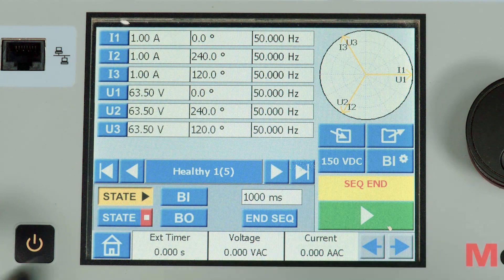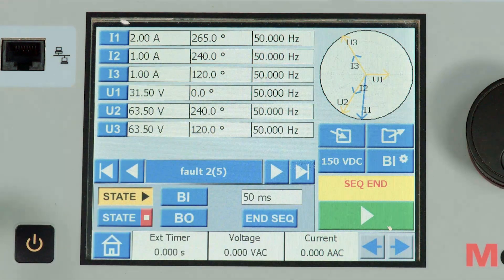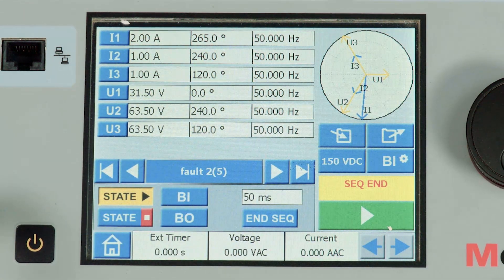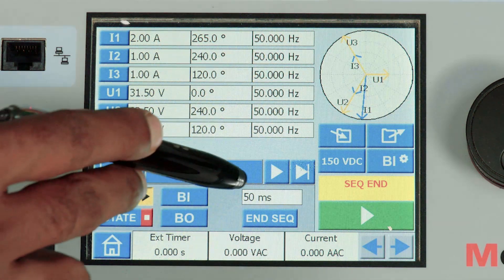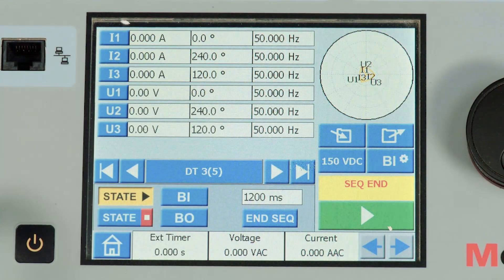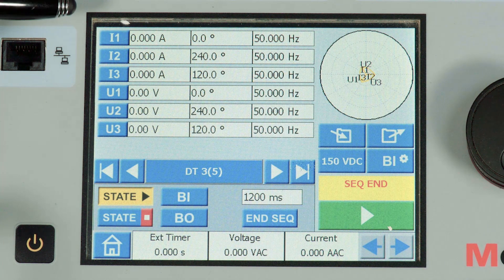State 2 is a fault state where an R phase fault is configured for 50 milliseconds. State 3 is the dead time for 1,200 milliseconds where no current and voltage is available.